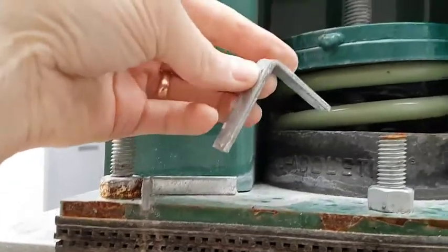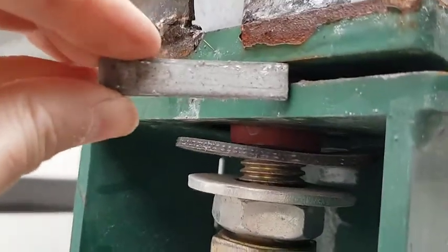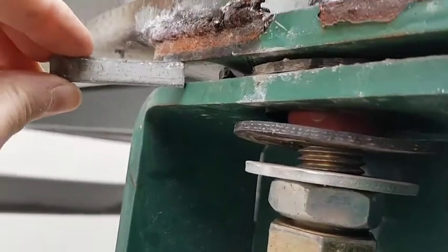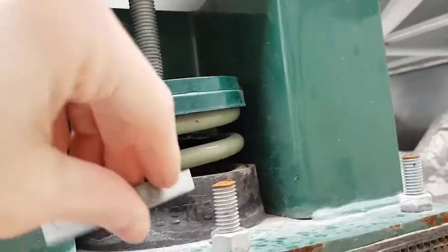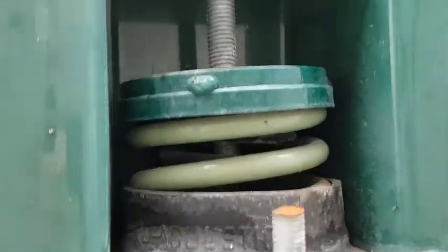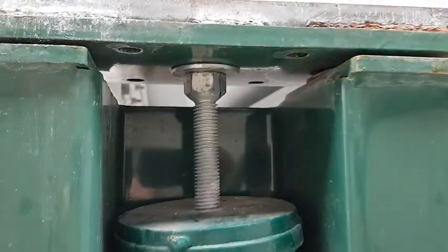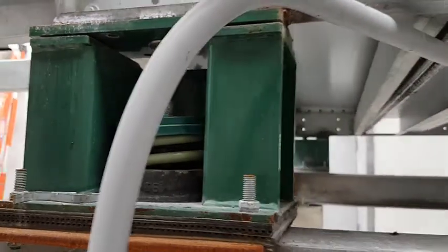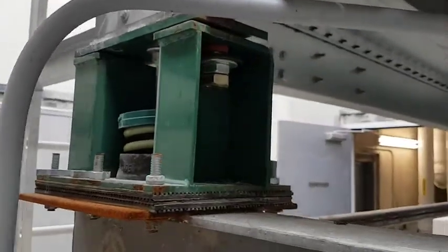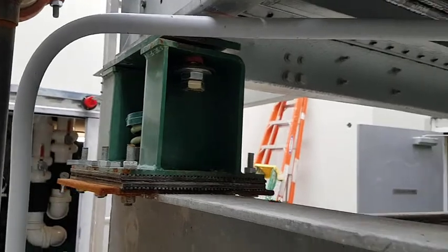Here is one of the spacers which are in place during shipment and initial installation. If the tower had been brought up to operating weight before the isolators were adjusted, this spacer would still be able to fit between the top plate and the hold-down plate. As expected for an SCSR 2A 1600, the outer spring is green and the inner spring is black. The springs have been adjusted and the spring compression cup is not in contact with the side stanchions.